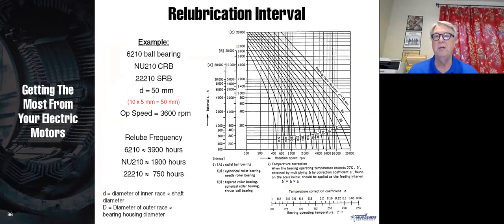This is a similar deal, and I won't go through it completely, but it gives you an example of a 6210 ball bearing. You take the 10 times 5, it's 50 millimeters, and then you find the speed of your motor. You go up to the 50 millimeters, then go across. And in this case, it has 3 on the left, a radial ball bearing, a cylindrical roller bearing, and a tapered roller bearing. So many manufacturers put out these little curves. Doesn't matter which one you use, they're all very good.